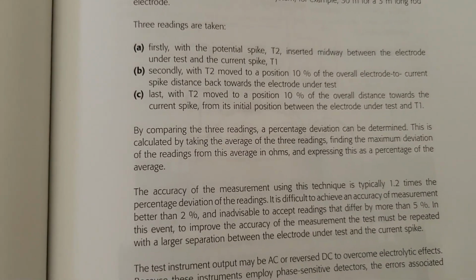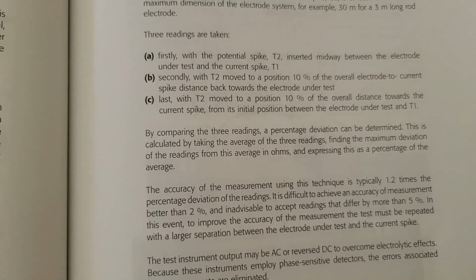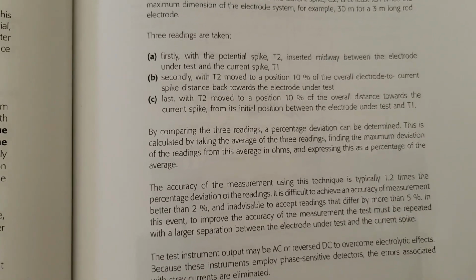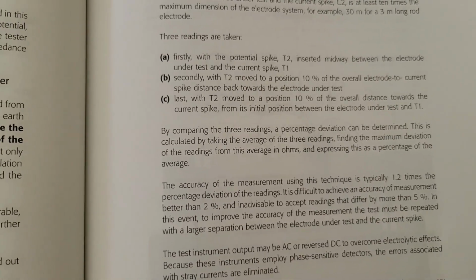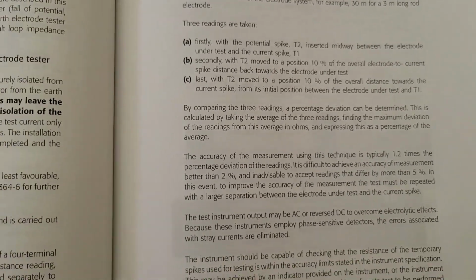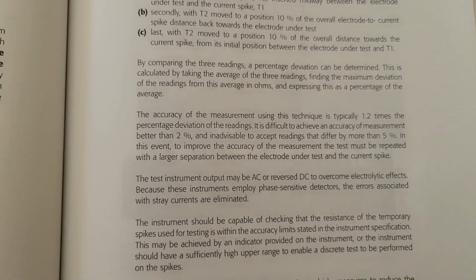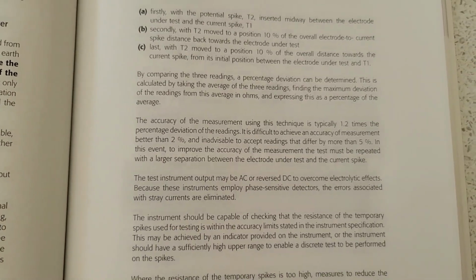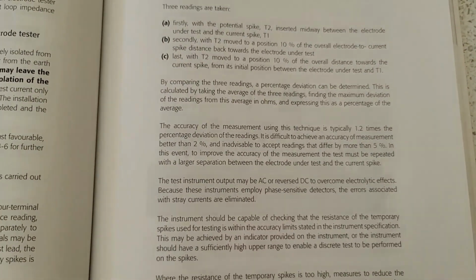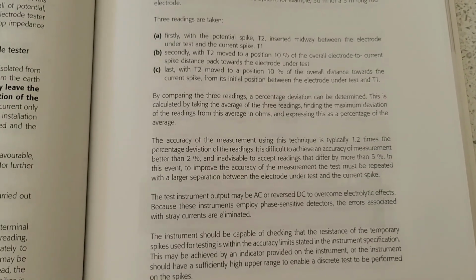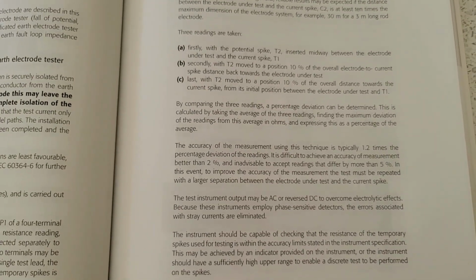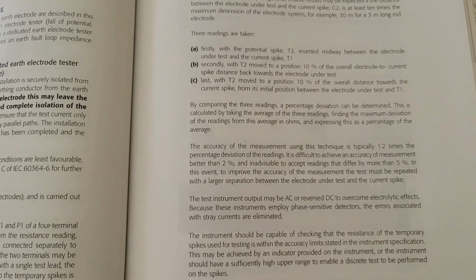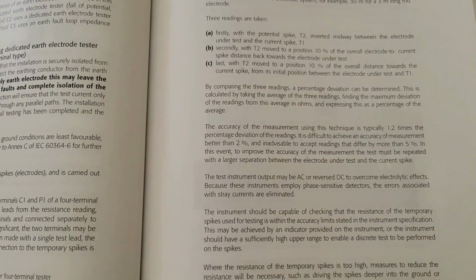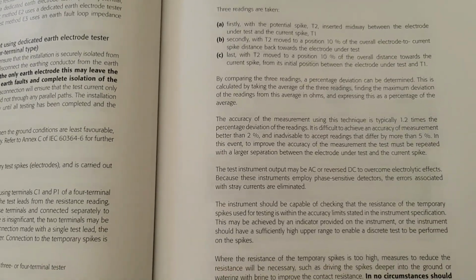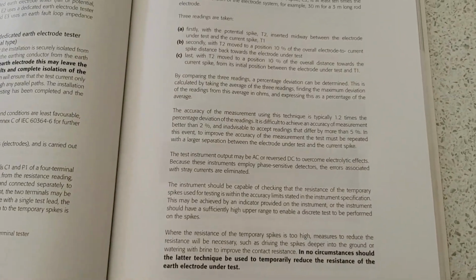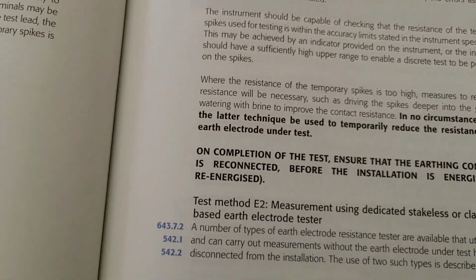And it says here, compare the 3 readings, a percentage deviation can be determined. This is calculated by taking the average of the 3 readings, finding the maximum deviation of the readings from this average and expressing this as a percentage. So that's one of the critical things you do need to do. And the accuracy of the measurement using this technique is typically 1.2 times the percentage deviation of the readings. So it's really difficult to get better than 2%, and it's inadvisable to accept readings that differ by more than 5%. So if you're getting huge variation, then the test you've done is probably of little value. So you need to look at how you've done it and see if you can adjust the way you're carrying out that test. Otherwise, use a different method to get a more accurate reading, I guess, is what this is suggesting. And yeah, it goes on to explain how you do that.